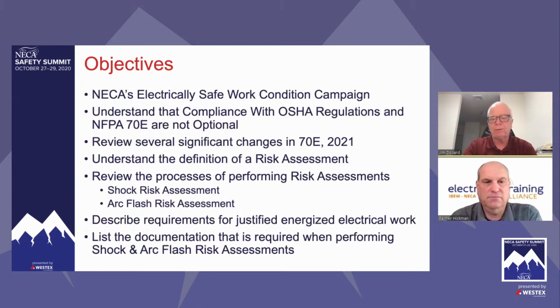And something else that is misunderstood fairly widely in the industry is the documentation of a shock and an arc flash risk assessment. NFPA 70E tells you in 130.4 that you must document all shock risk assessments. In 130.5, we tell you that you must document all arc flash risk assessments. And we're all very familiar with the requirements for energized electrical work permits. When we fill out an energized electrical work permit, it's going to require that we document the shock risk assessment and the arc flash risk assessment on that form.